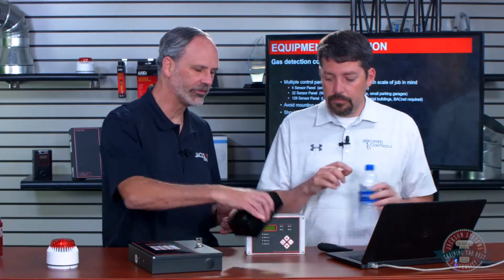It's got an Android tablet in it. But the nice thing about that one is just the sheer size of it and the fact that it can communicate via BACnet if we need it to. However, Joe, I want you to talk about communicating with a building automation system with gas detection. So there's a couple ways to go about it. These sensors use their own little proprietary communication protocol, and they talk directly with one of these 2 panels or even the larger one. But this same sensor is available with BACnet.